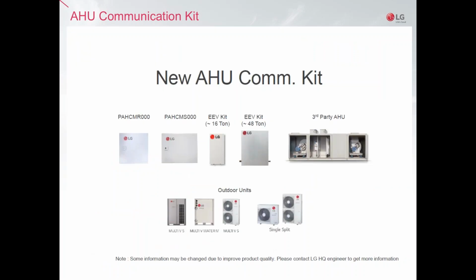So as I said, the layout is simple. You only need a new or existing air handling unit or DOAS. Verify that the design conditions of entering air temperature, leaving air temperature, and CFM are within the specifications of the product. Select a third-party DX coil based on the selection tables provided by LG, and just add the right combination of VRF equipment, EEV, and communication kits, and it's as simple as that.